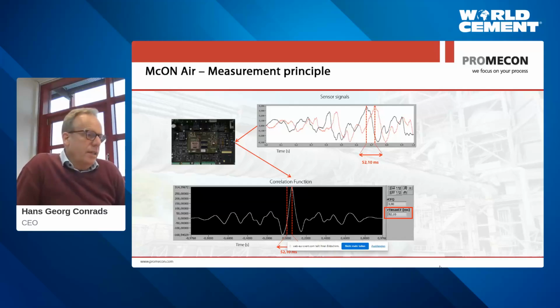And that pretty much is already it. So you divide the distance of the sensors, let's say 300 millimeters, by the time of flight, 52 milliseconds, and out you get meters per second. Very simple, right? Millimeters divided by milliseconds gives you meters per second. And that's basically the velocity of the gas in the duct. Now, this method of measurement is radically different from other methods, such as differential pressure measurement, which is basically measuring the pressure if you put a venturi into the duct, or if you put a pitot tube into the duct.